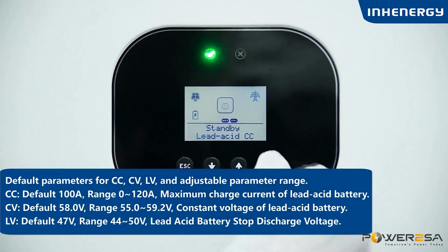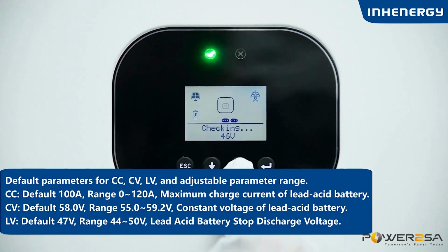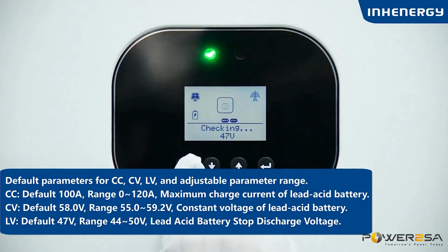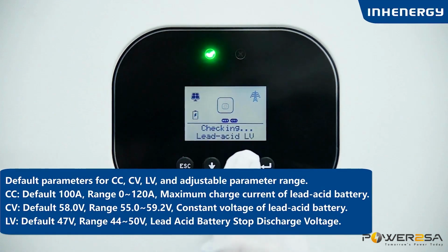CC default 100 ampere, range 0 to 120 ampere, maximum charge current of lead-acid battery. LV default 47 volts, range 44 to 50 volts, lead-acid battery stop discharge voltage.